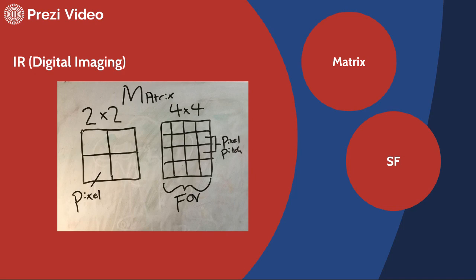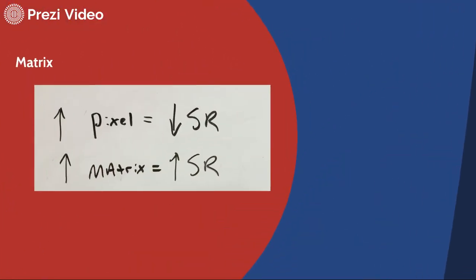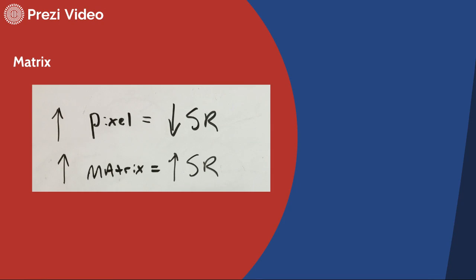Let's talk about it now from this viewpoint of the image receptor. Spatial resolution from this viewpoint is a totally different concept. It has to do largely with the matrix size, and when I say matrix size, I'm talking about binary numbers. For example, this matrix here on the left has very large pixels. It's a two by two matrix, meaning two to the power of one times two to the power of one, and so we have a total of four little pixels there. The pixel just means a picture element versus this other matrix. It's considered a larger matrix, even though the field of view they're covering is roughly the same. But it's a larger matrix because it's two to the power of two, so it's a four times four matrix. Therefore, the pixels are smaller. One of the ways that we measure that in terms of spatial resolution is this pixel pitch, which is the distance from one pixel to the next.